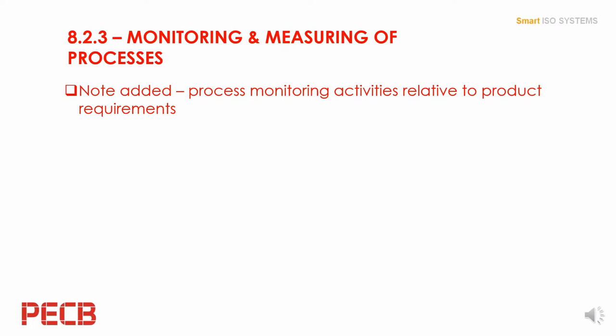The calibration monitoring tool used in process might be different from the calibration monitoring tool used for final inspection for releasing your product. You will be required to justify how tight your controls are based on the circumstances and the complexity of each process.